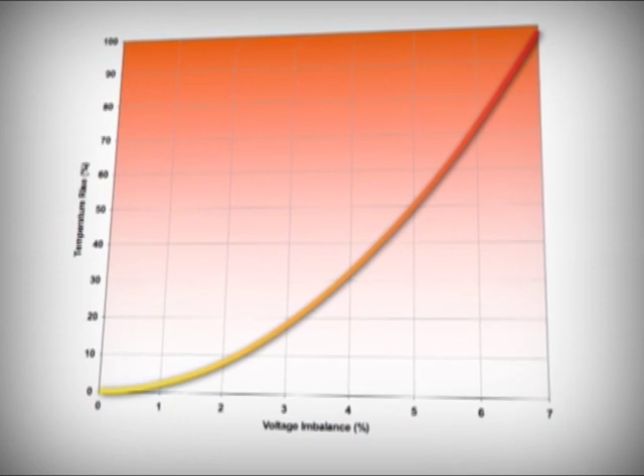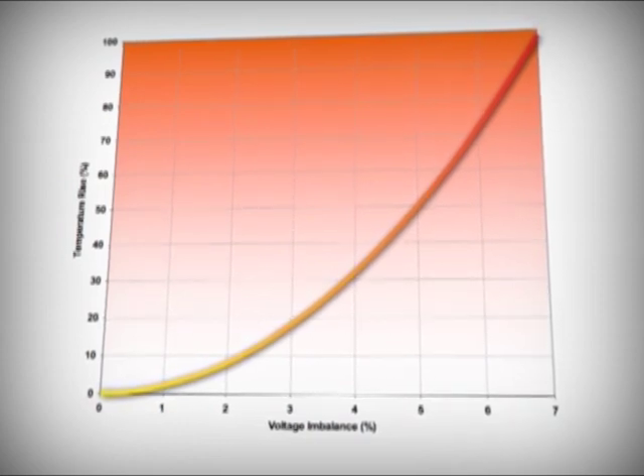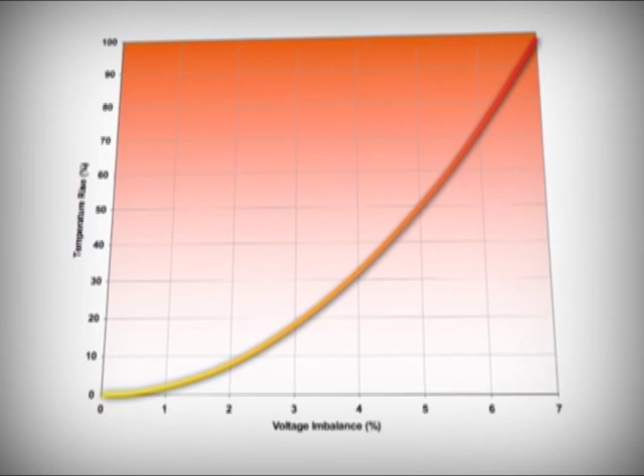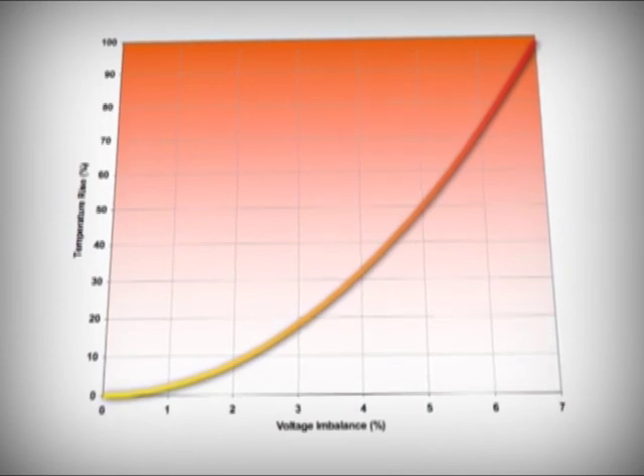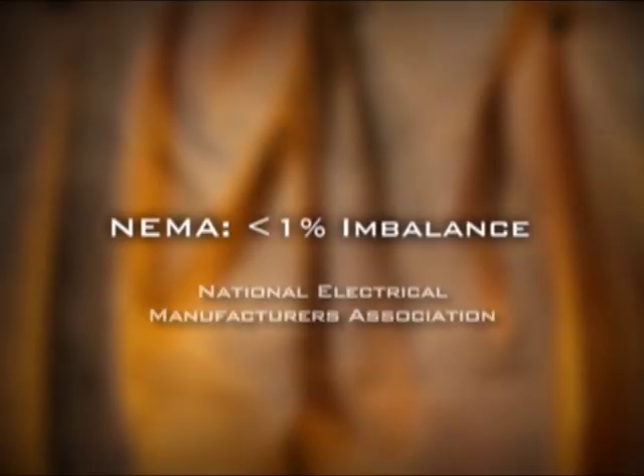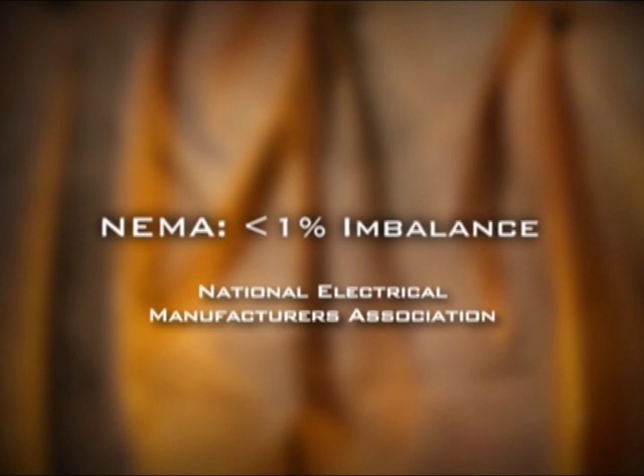Even a slight voltage imbalance causes a significant temperature increase in the windings. As the imbalance grows worse, the temperature skyrockets. And that's bad news for compressors, because operating a motor at 10 degrees centigrade over the rated temperature cuts its life in half. Phase balance is so important that the National Electrical Manufacturers Association recommends no more than a one percent imbalance for motors operating at full load.